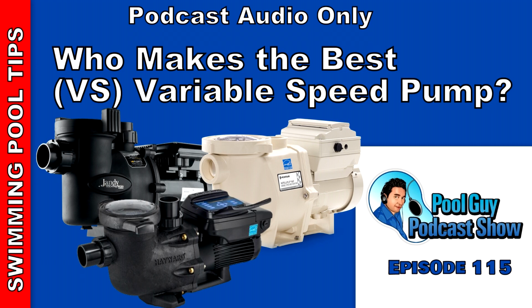They also make a Superflow pump, which is really great because this pump runs what they call a dual voltage. So you can connect it to 230 volts or 115 volts. So if you have a single breaker on your old pump and you're running at 110 volts, you can definitely connect the Pentair Superflow VS pump to it with no problem. I'm not sure how it works. Somehow it throttles the voltage when you connect it, because you wire it the same way as you would wire for 230 volt wiring, and so something inside the pump itself will throttle the voltage down so that you won't have any problem running it.